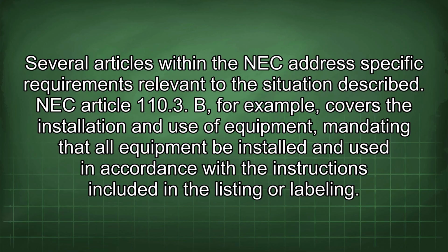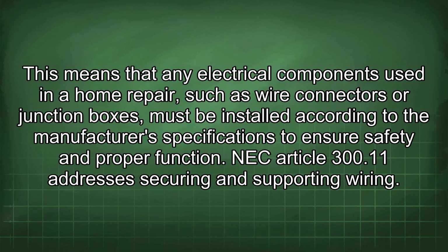NEC Article 110.3(B), for example, covers the installation and use of equipment, mandating that all equipment be installed and used in accordance with the instructions included in the listing or labeling. This means that any electrical components used in a home repair, such as wire connectors or junction boxes, must be installed according to the manufacturer's specifications to ensure safety and proper function.